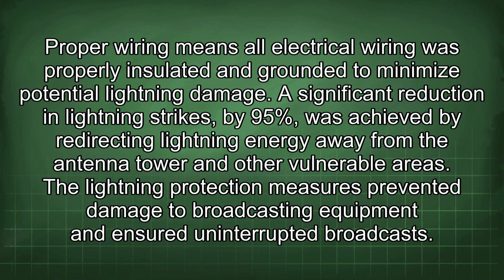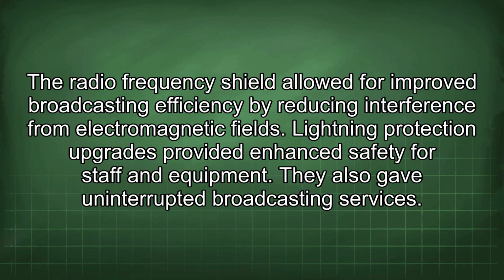A significant reduction in lightning strikes, by 95%, was achieved by redirecting lightning energy away from the antenna tower and other vulnerable areas. The lightning protection measures prevented damage to broadcasting equipment and ensured uninterrupted broadcasts. The radio frequency shield allowed for improved broadcasting efficiency by reducing interference from electromagnetic fields.